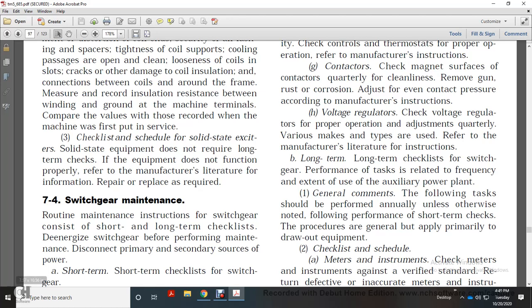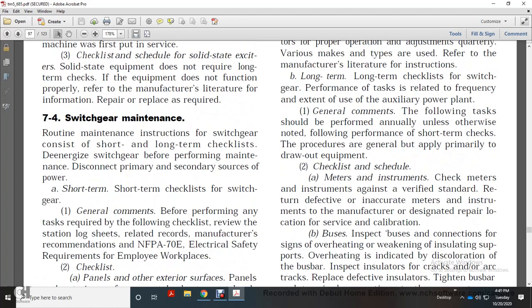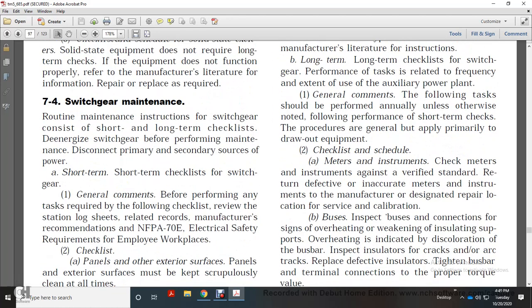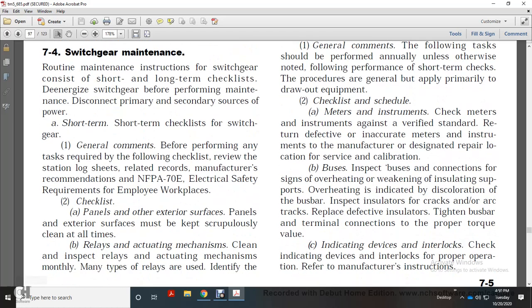Routine maintenance instruction for switchgear: consider the short and long-term checklist. De-energize switchgear to perform maintenance, and disconnect primary and secondary sources of power from the switchgear. Before performing any of the tasks required in the following checklist. Review the station log sheets, related records, manufacturer recommendations, National Fire Protection Association 70E electrical safety requirements, and the employee workplace checklist.